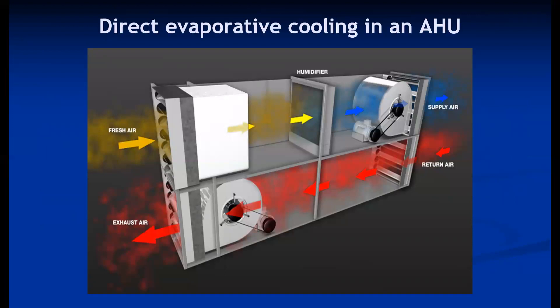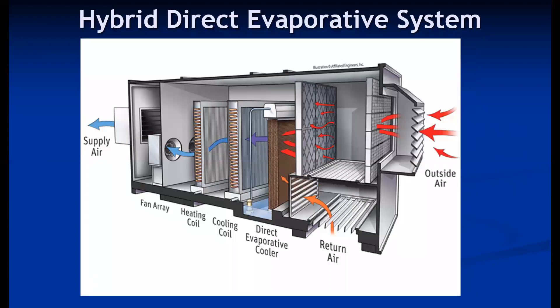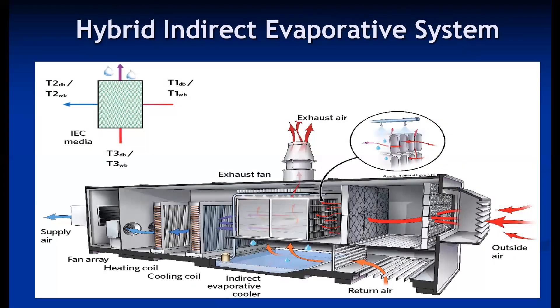These are some models of AHUs fitted with humidifiers, and this is an AHU fitted with a direct evaporative cooler along with a cooling coil and heating coil — this is called a hybrid air conditioning system. The direct evaporative cooler is used for humidification, while the cooling coil provides additional cooling and the heating coil handles heating applications. This is the hybrid direct evaporative cooling system. In the hybrid indirect evaporative cooling system, an indirect evaporative cooler is installed followed by a cooling coil and heating coil.